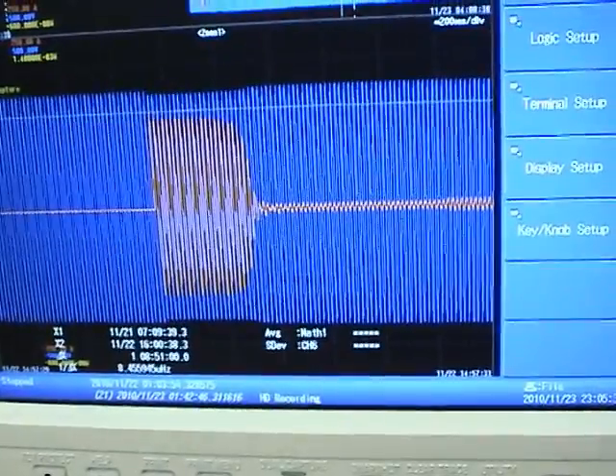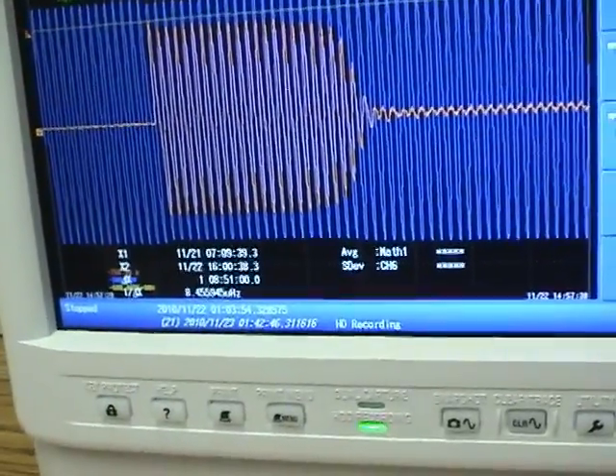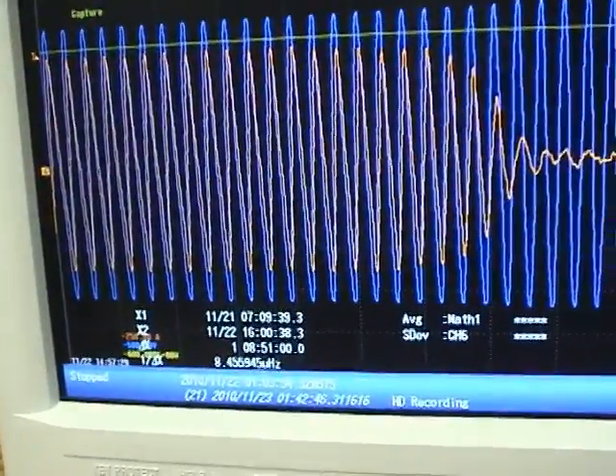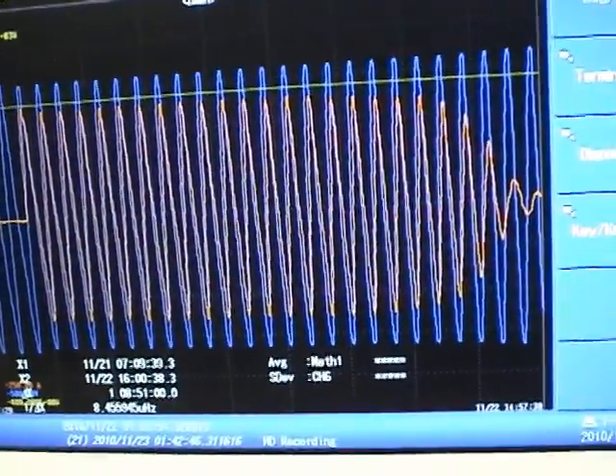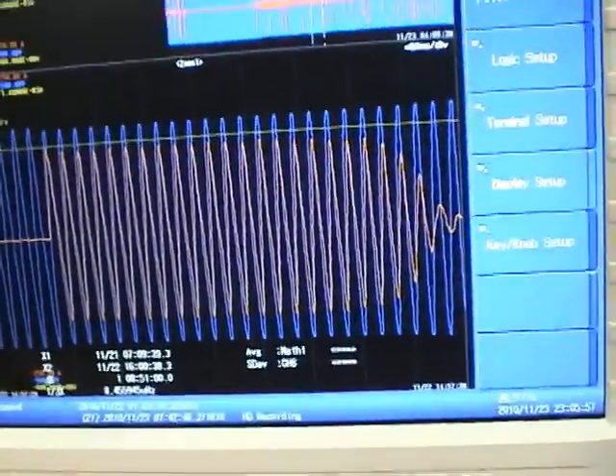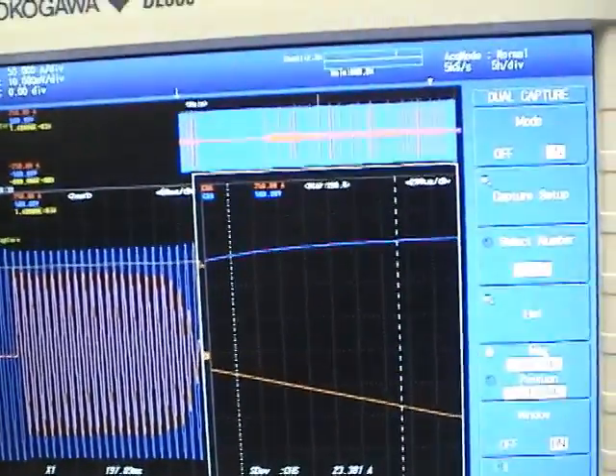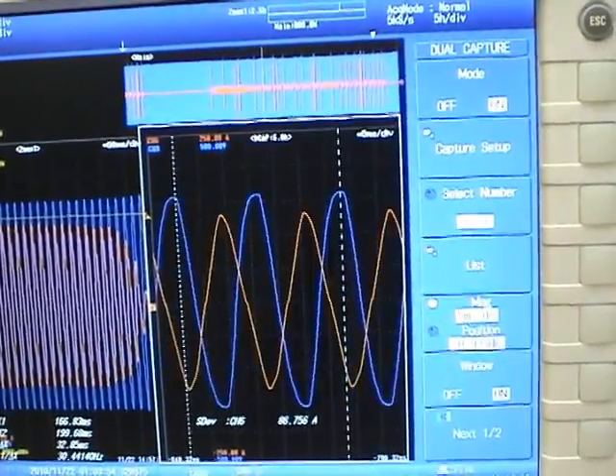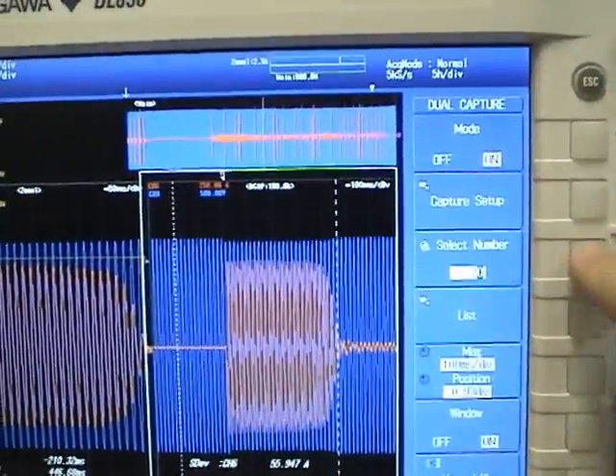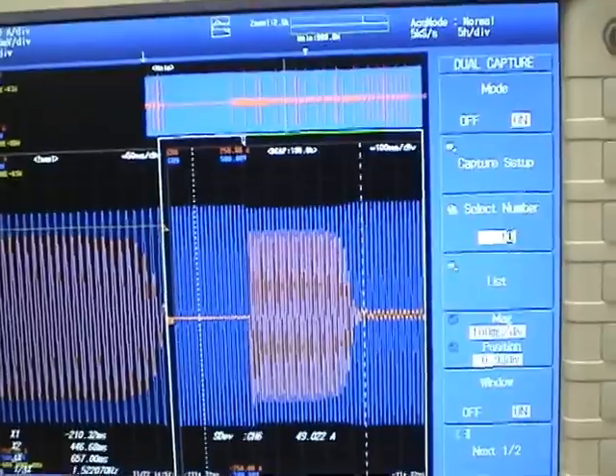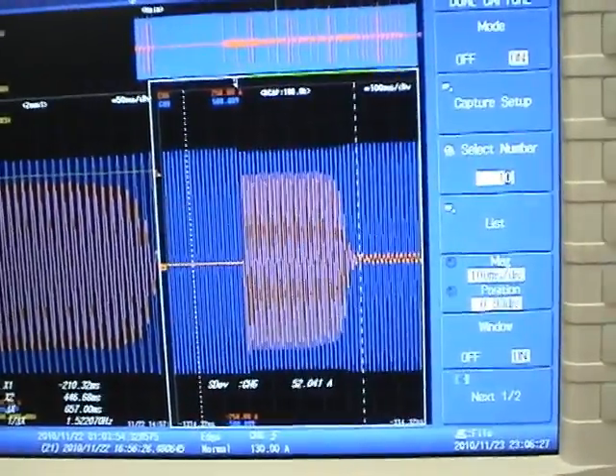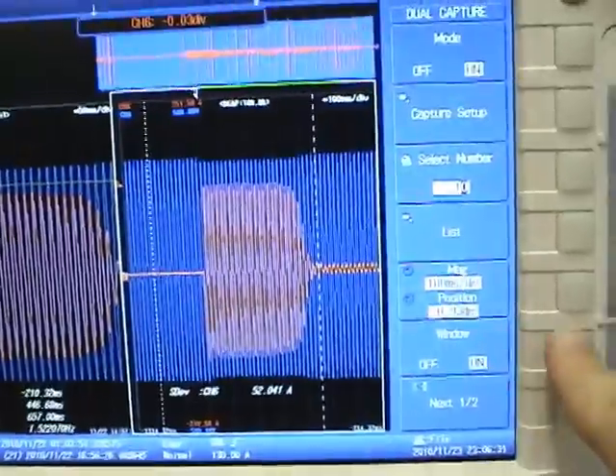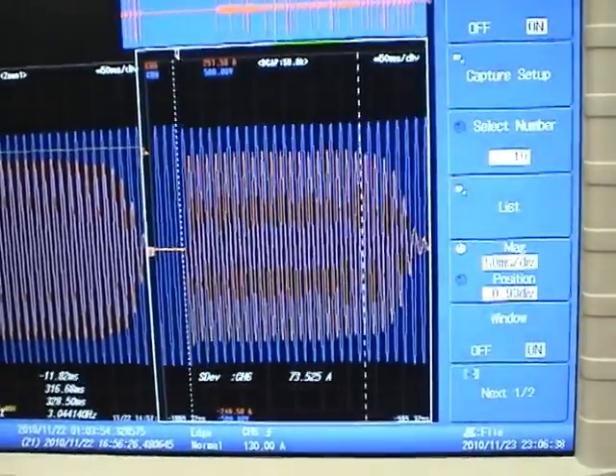Let's see this is at I think 50 amps per division. So you know the compressor draws something like 100 amps RMS during startup for 300 or 400 milliseconds or so. And let's see also what the dual capture got. That should have captured every turn on. Let's just zoom out on this. And now let's go through the list. There's every single turn on of the compressor sampled at how fast did we sample 100 kilosamples per second.